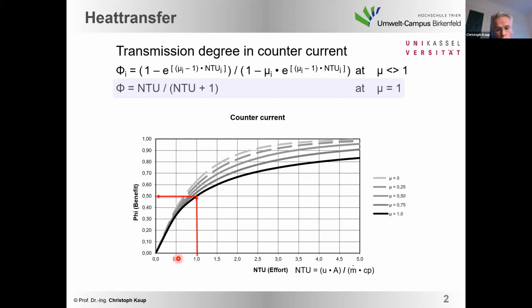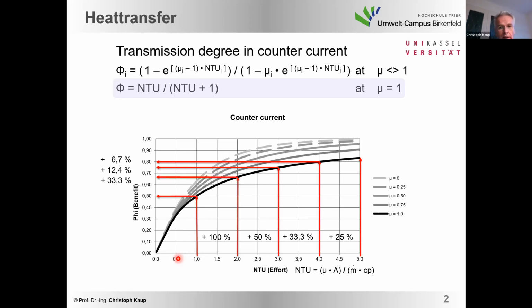Very easy. What happens if we double our effort, our NTU? If we take an NTU of 2, that might be 16 rows of a round coil in your air handling unit. Unfortunately, we then have double the effort, double the pressure losses, but we don't have double the benefit. We don't have 100% efficiency. Now we will have an increase to 67% efficiency, and so on. If we go to an NTU of 3, that might be 24 rows, we will have 75% efficiency, and 8 rows more will lead to 80%, and an additional 8 rows more will lead to 83% efficiency.